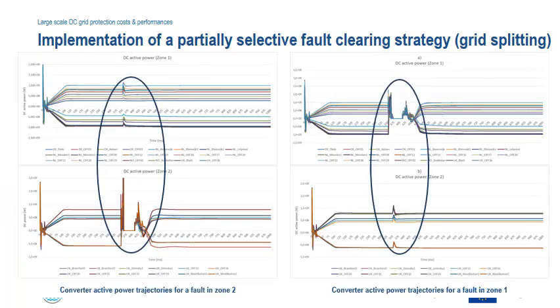These two figures show an example of the trajectory of the active power at all AC-DC converter terminals during the protection and grid restoration process obtained in the two protection zones. As expected, it can be observed that only the converters belonging to the faulty zone experience a temporary full power flow interruption. The non-faulty zone is not affected.